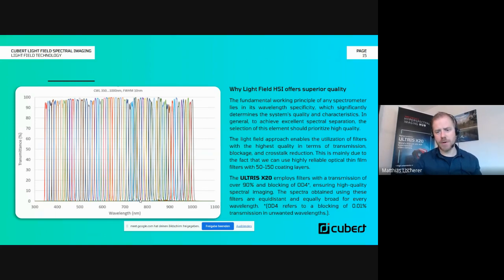Another advantage of this approach is that it comes with very high quality. What you see here is the transmittance of the optical bandpass filters that are used in the Ultris X20, our major model with the 20 megapixel sensor. On the y-axis, we see the transmittance in percentage, and on the x-axis, the wavelength range our camera covers. It starts in the ultraviolet at 350 nanometers and goes through the entire visible range, covering the entire near infrared. Near infrared is not clearly defined, but typically you can say up to 1000 nanometers is near infrared. Everything after 1000 nanometers is known as shortwave infrared, typically going up to 2500 nanometers.